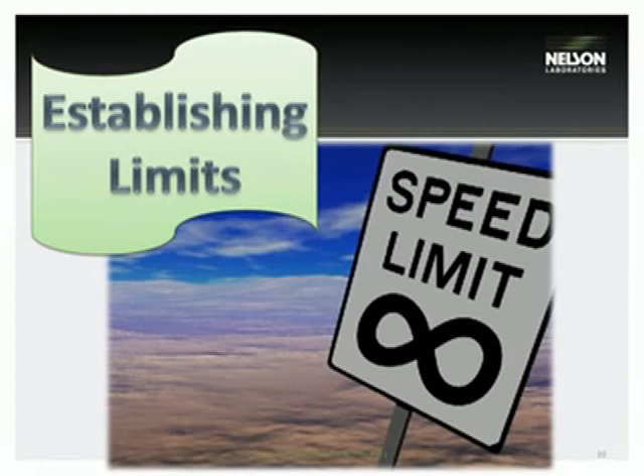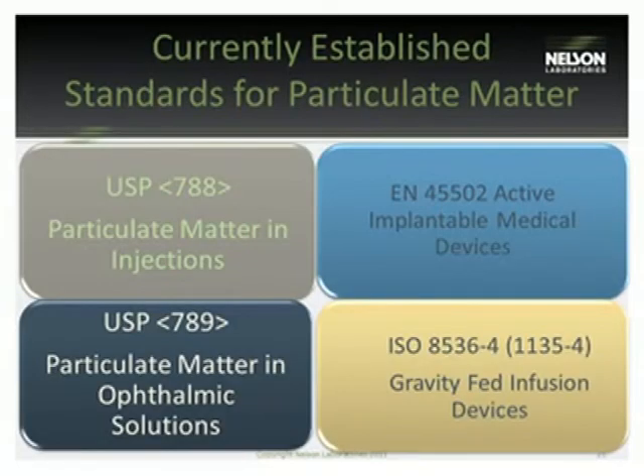Now, establishing limits is a bit of a gray area currently in particulate testing because there are no set limits for most medical devices. Limits do exist for small groups of devices, as well as for liquid samples via the USP 788, which we'll go over briefly. But for most cardiovascular devices and implantables, limits do not currently exist, and so they must be established by manufacturers or other standards or specifications adopted to your device. So TIR 42, which we'll also go over briefly, gives some details regarding establishing limits, and we'll touch on that in a few minutes. There are some particulate matter standards that do exist.